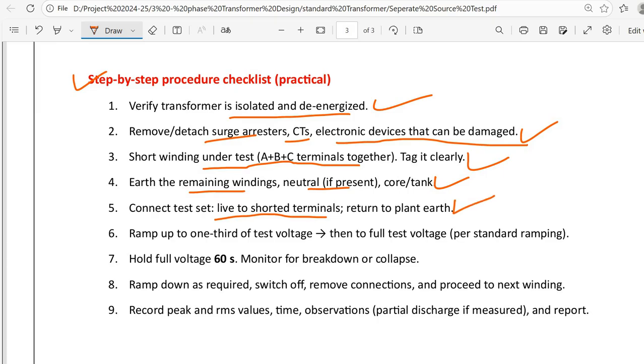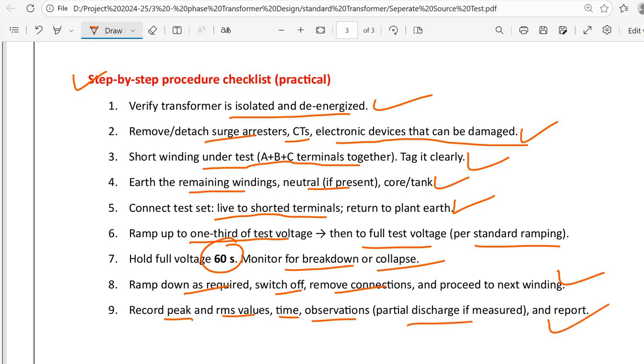Ramp up to one third of the test voltage, then to the full test voltage as per standard ramping. Hold for 60 seconds and monitor for breakdown or collapse. Ramp down as required, switch off, remove the connections and proceed to the next winding. Record peak RMS, time and observations. Partial discharge is measured and reported. So these are the steps to perform the separate source test of the transformer.